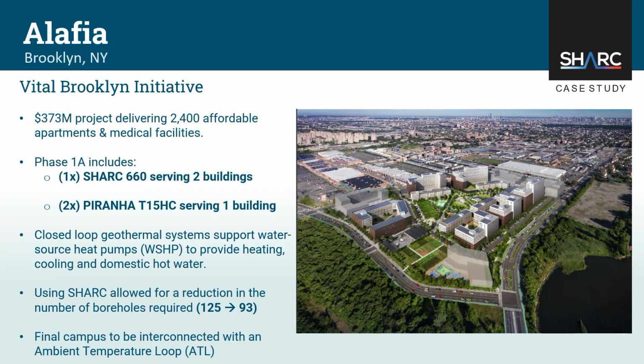And we have 2 Piranha HCs in the basement of C3 producing 100% of the domestic hot water load for said building using a combination of the sanitary and the geothermal. So in the wintertime, when that geo loop is pretty cold because they're taking all the heat out of the loop to heat the apartments, we're using the 72 degree some odd Fahrenheit wastewater from the toilet, showers, and sinks in the building to make 140 degree potable hot water for the building. And in the summertime, when that loop gets heated up to about 90, 95 degrees because everyone is now pushing heat from the heat pumps into that loop, the Piranha is programmed to switch over to the loop to pull energy out of the loop to make the potable hot water. So between those 2 systems, we're able to produce 100% of the domestic hot water load for C3.